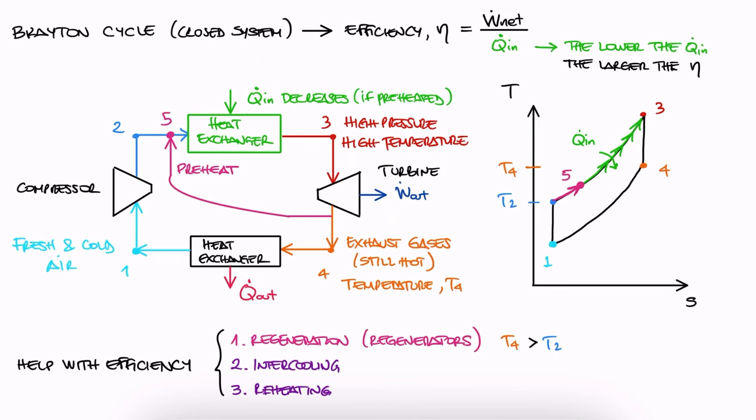This is what the regenerator does. Takes heat from 4 and transfers as much as it can to 2, so that Q in is not as high as it would've needed to be. As you can probably already tell, a regenerator is nothing more than just a heat exchanger. The regenerator brings in the hot gases from 4 and the cooler gases from 2 and allows them to exchange heat.